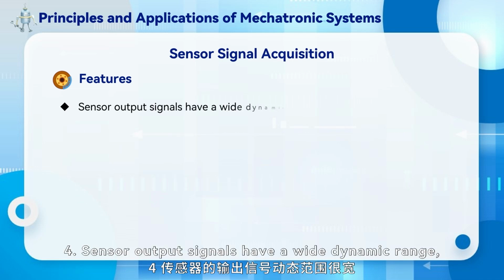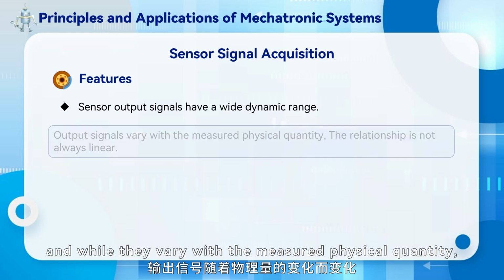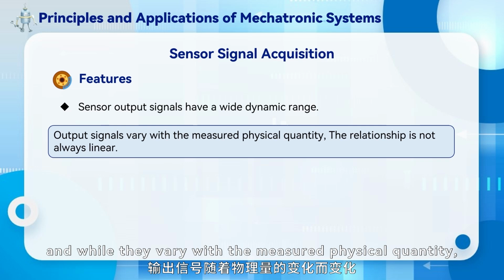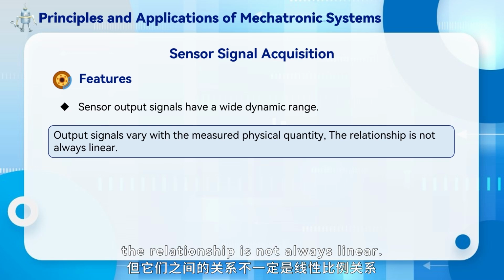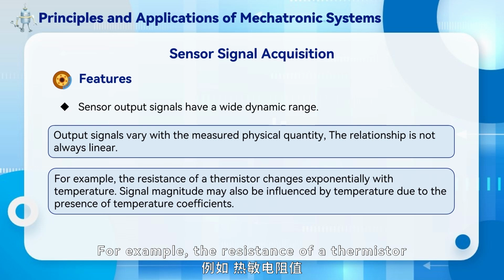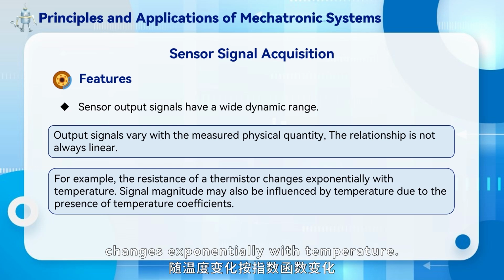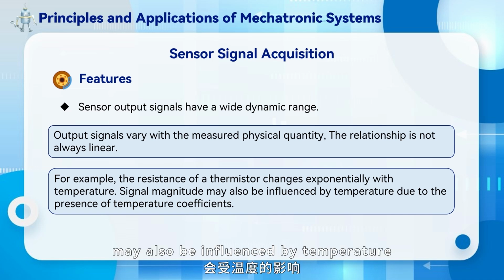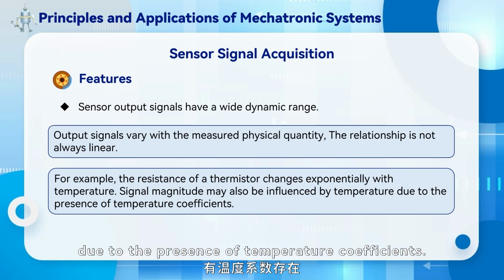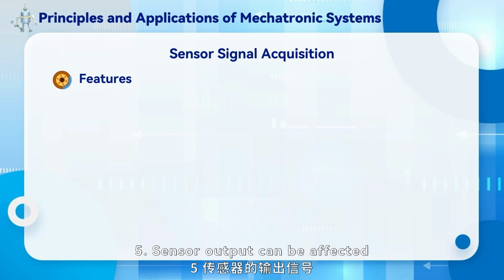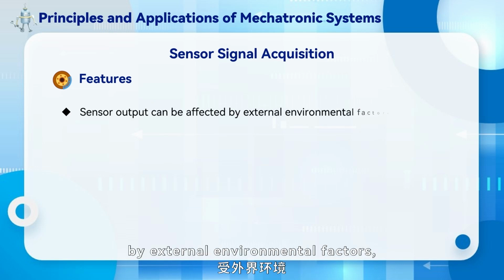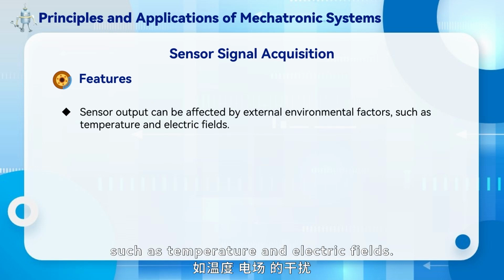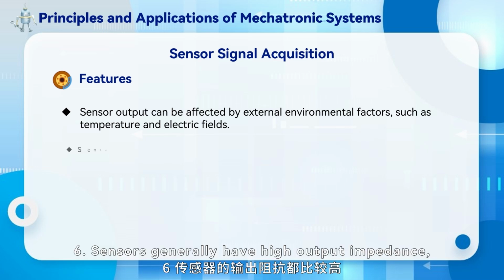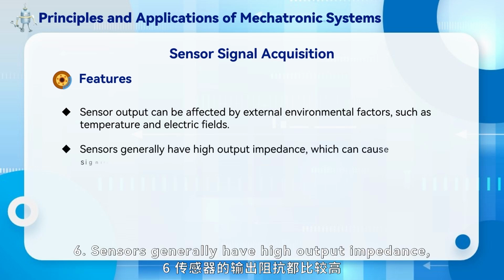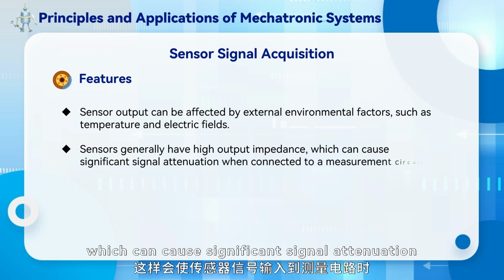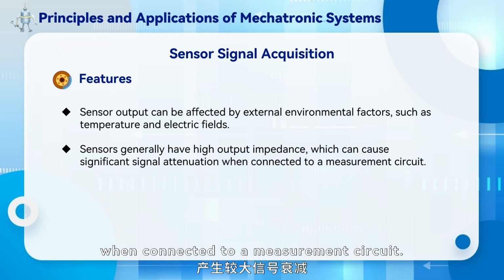4. Sensor output signals have a wide dynamic range, and while they vary with the measured physical quantity, the relationship is not always linear. For example, the resistance of a thermistor changes exponentially with temperature. Signal magnitude may also be influenced by temperature due to the presence of temperature coefficients. 5. Sensor output can be affected by external environmental factors, such as temperature and electric fields. 6. Sensors generally have high output impedance, which can cause significant signal attenuation when connected to a measurement circuit.